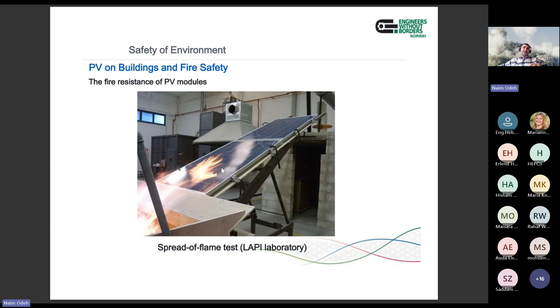There are some recommendations that I'm highlighting here about actions to be taken in case of fire. So you can consider something called a manual call point. You can consider this point in case of fire. Take the first scenario: if you have fire happening at the roof, you see the manual call point. It disconnects the DC, which is the safest one, so it disconnects the DC from the rest of the system. That means this part is isolated. When you disconnect, you protect these items not only from fire, but also from overheating or other abnormal current flow to the system. And also you protect the rest of the system.